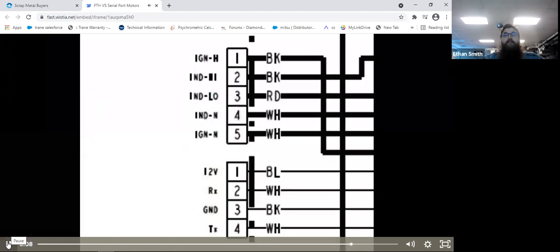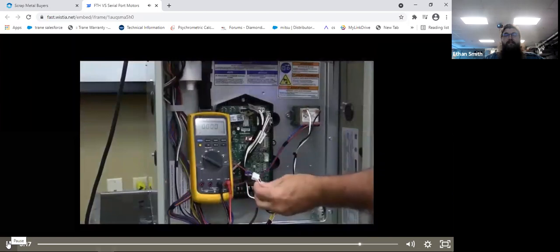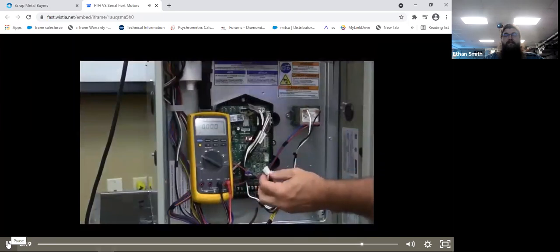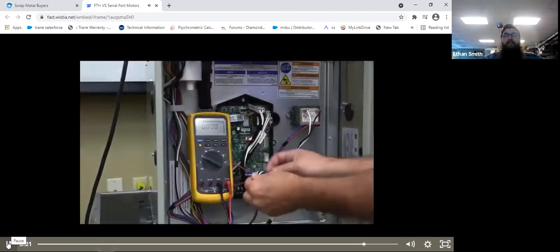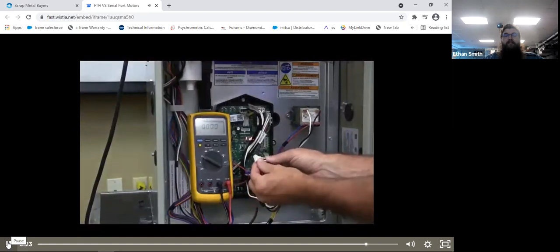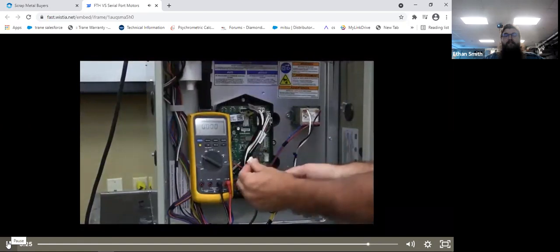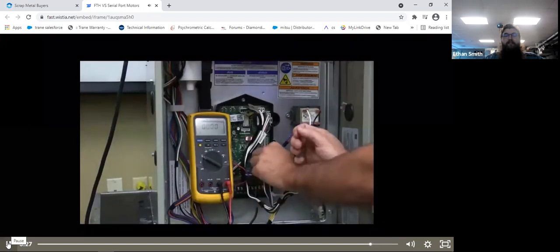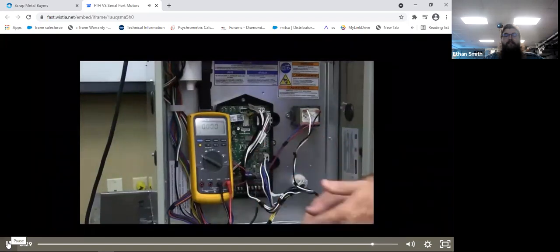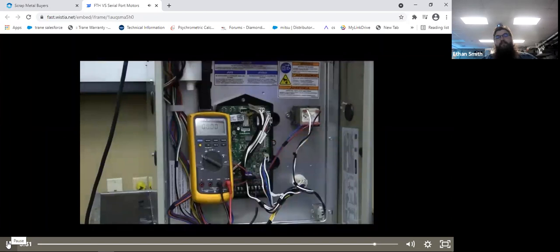Now, if I'm seeing a transmit pulse, but I'm seeing no receive pulse, then I know that I either have a broken wiring harness or my motor has failed. I'm going to remove the wiring harness at both ends, ohm out each one of the individual wires. Make sure my pin connectors on each one of the wires are tightly seated within the Molex plug. And if my wiring harness is good, then I know that my issue is with the motor itself, and I will be replacing the motor.